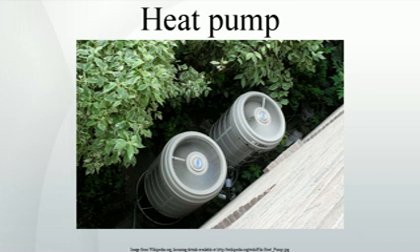In electrically powered heat pumps, the heat transferred can be 3 or 4 times larger than the electrical power consumed, giving the system a coefficient of performance, COP, of 3 or 4, as opposed to a COP of 1 for a conventional electrical resistance heater, in which all heat is produced from input electrical energy.